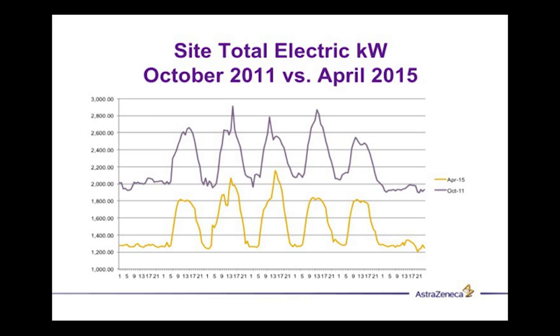The nice thing about this, what we talk about consistently, is that because we dropped down from 2,600 to 1,800, there's 800 kW. It's also less money that we have to pay in demand charges. $22 per kW in the summertime, 18 in the wintertime. That's a lot of money right off the bat.